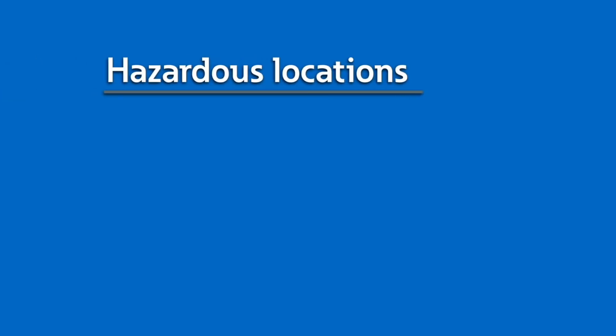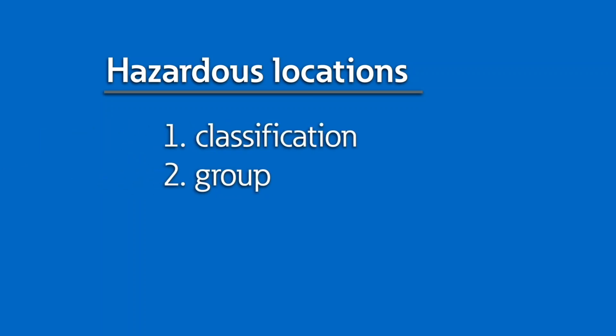Hazardous locations are classified based on 3 categories: classification or type of combustible fuel. Groups are nested within classifications, which are sorted based on combustion characteristics. And finally, divisions, which consider the presence of flammable fuels within the operating environment as normal or abnormal. The National Electrical Code 500 is one of the governing code models that defines the division system that we'll be discussing here. Let's begin with classification.